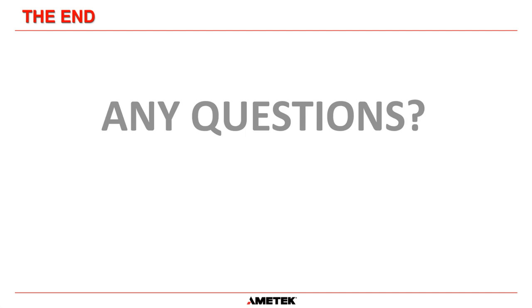Oh, one more question has just popped up. What is typical THD for the DSC and DPP design? Off the top of my head, I think for the DSC it's 5% and for the DPP is 2%, but let me see, have I got the DSC paperwork here? Okay, yeah, for the DSC it's less than 5%. I'm pretty sure for the DPP it is less than 2%.